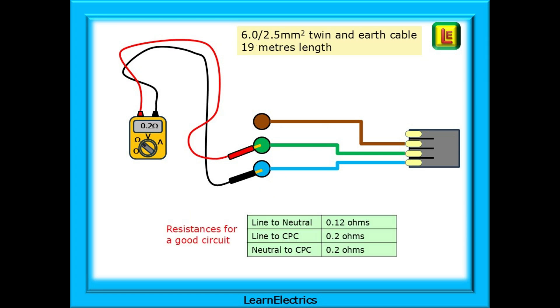Putting these into a little table — and it's good practice to write things down, don't trust to memory. We have line to neutral at 0.12 ohms, line to CPC at 0.2 ohms, and neutral to CPC also at 0.2 ohms.